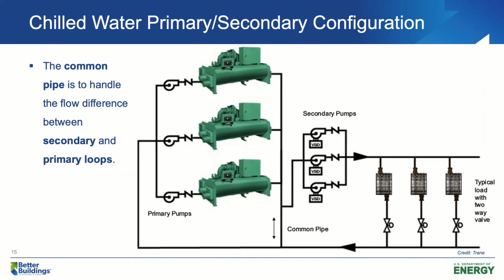There are two major configurations on the water side. One is a primary and secondary configuration, and the other one is a primary only configuration. In the old times, chillers could not handle variable water flow through the evaporators, so we have primary pumps to circulate the same amount of water all the time to make sure that our chillers will work properly. However, when cooling load drops, we will use our secondary pumps with the help of VFDs to modulate the pump speed and chilled water flow to match the cooling load.